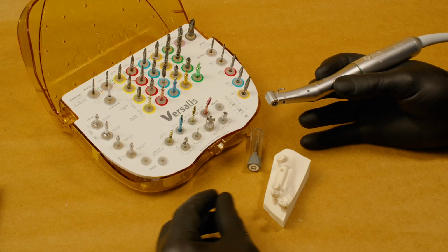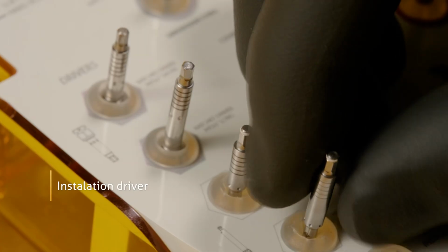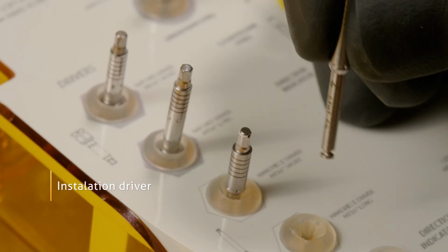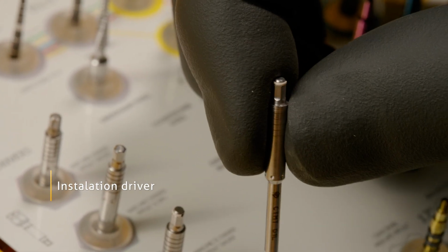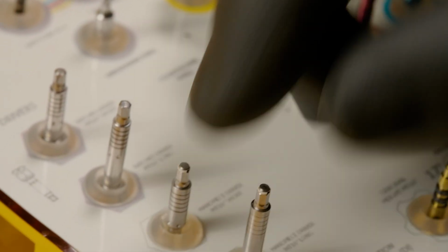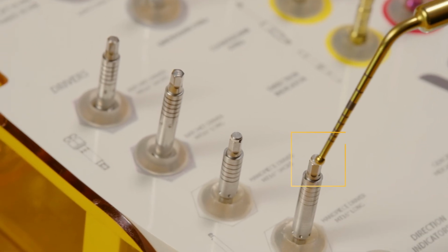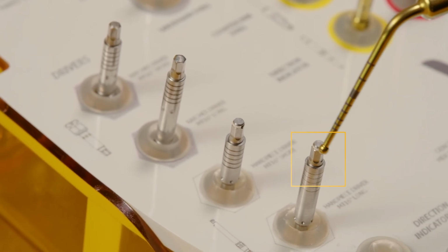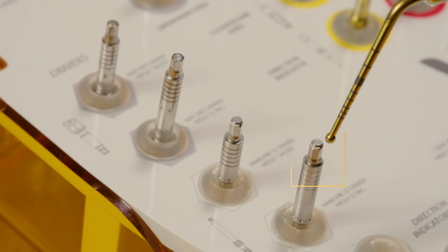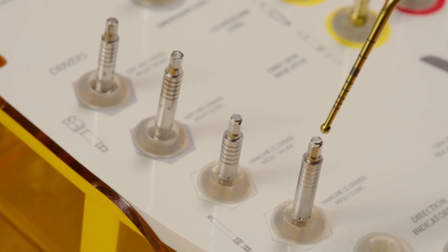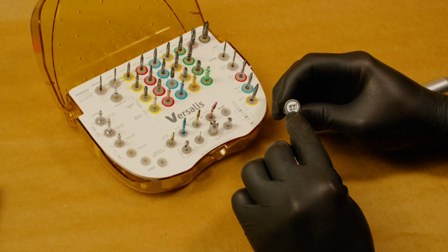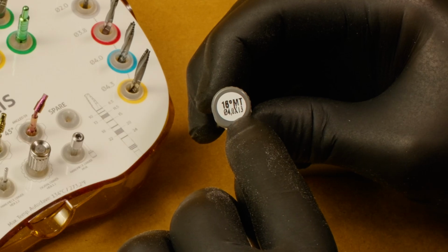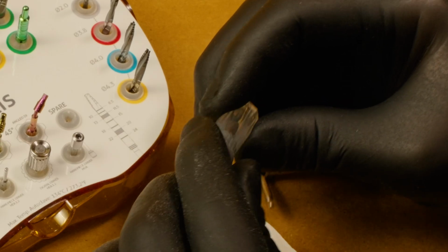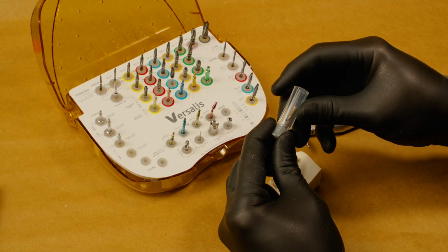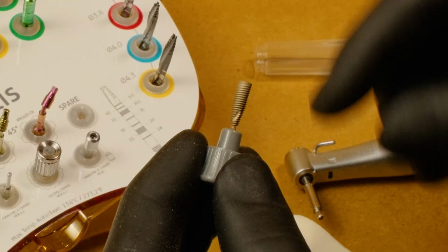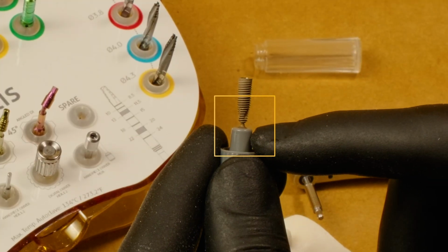For implant placement, we need the installation driver. Please note that this driver features a tip made of PEEK material, which is specifically designed for this purpose. This allows for better adaptation and helps to hold the implant more securely and firmly in the driver. On the implant cap, you can clearly see the selected size and its connection type, which are important details to verify. To open it, you need to turn it a quarter of a turn, and then the implant is securely held in place with a strong titanium connection.